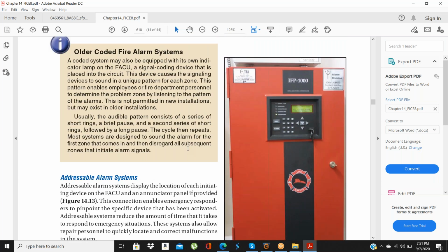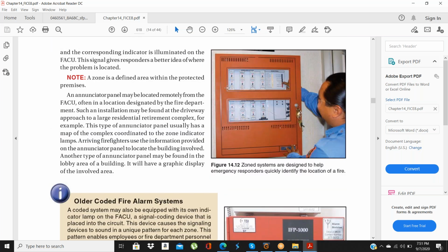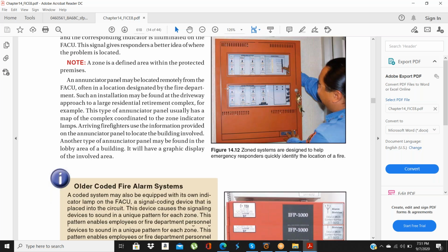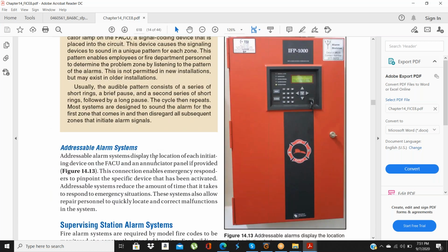This zone system only shows the zone, but maybe in that zone there are 4 or 5 detectors. The addressable alarm system will show you exactly which fire detector has the problem or where the fire is. If there are rooms 1, 2, 3 with detectors A1, A2, A3, and there is a fire in room 1, it will show that detector A1 is activated and the fire is in A1. That is called an addressable alarm system.